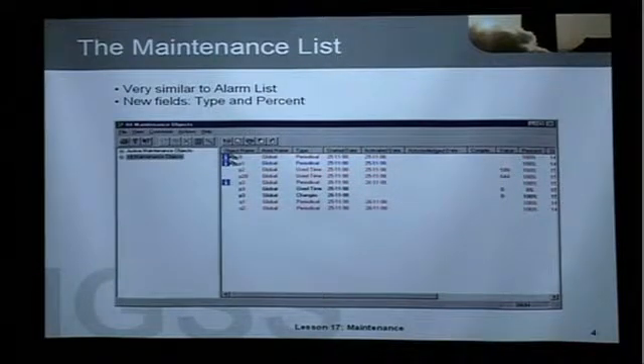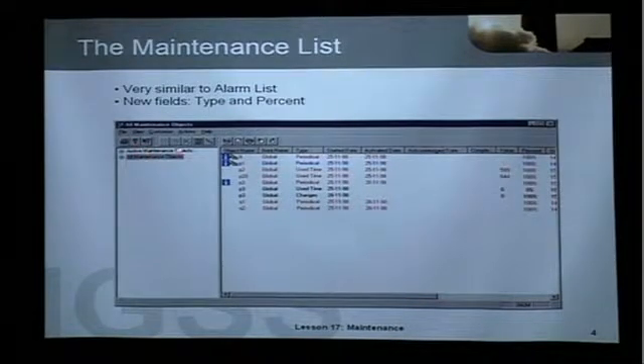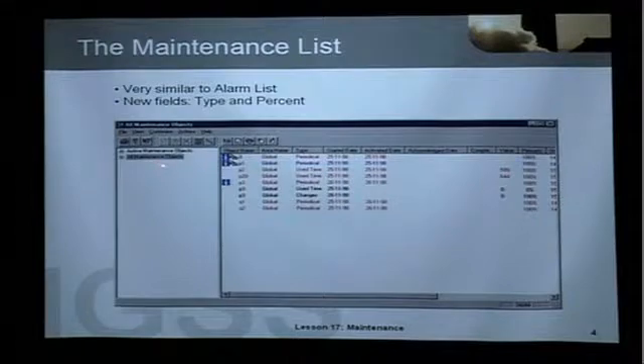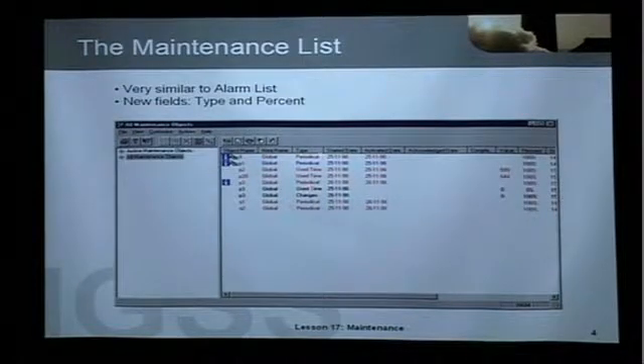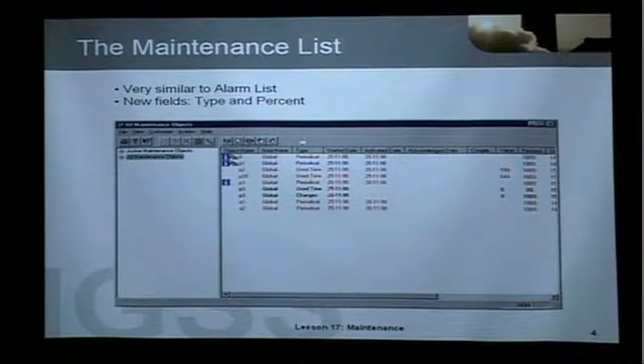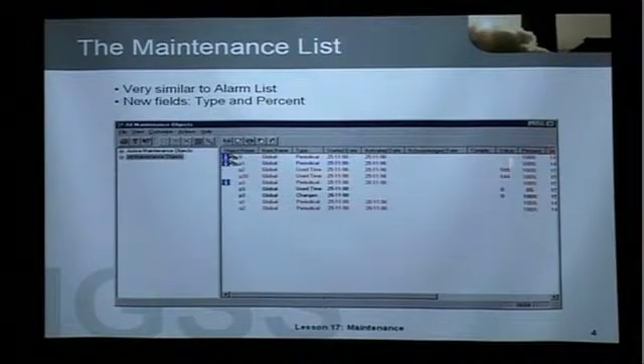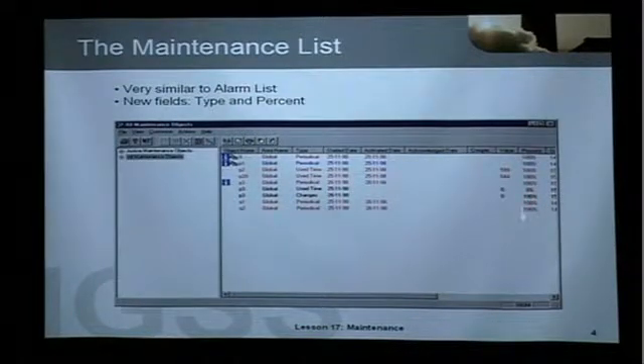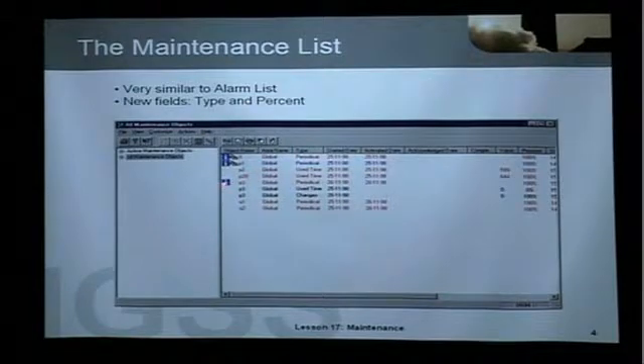This is the maintenance list. It is very similar to the alarm list that we have already looked at. We have a tree view, with active maintenance objects at the top and all maintenance objects below, which corresponds to the alarm log in the alarm list. We have two new fields: the type field, where you can see periodical, use time, and changes, and a column called percent, which shows how many percent of the maintenance interval has expired. 100% means the maintenance job is active now. You can also see an info icon — this means there are instructions attached to this maintenance job.